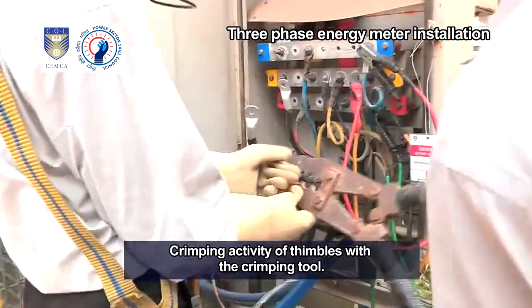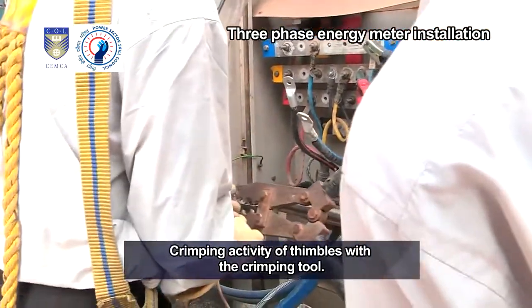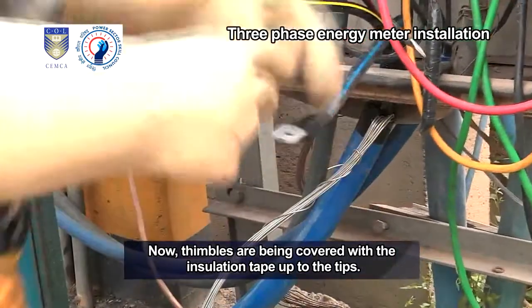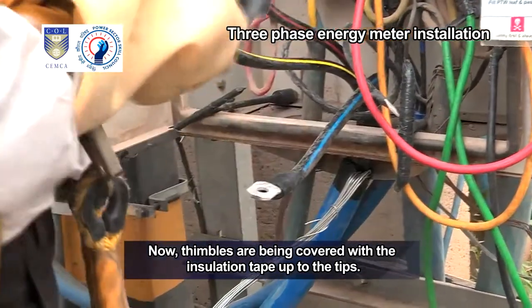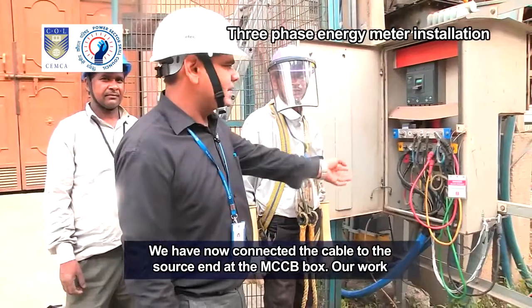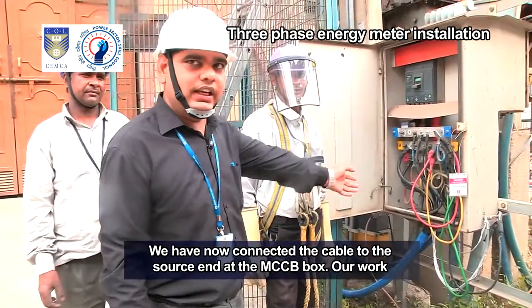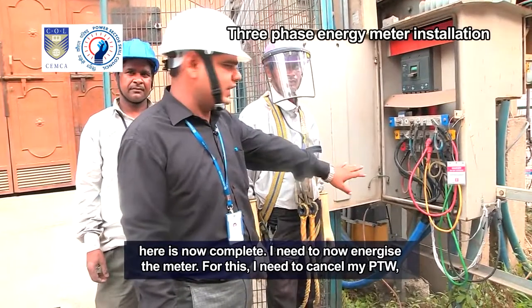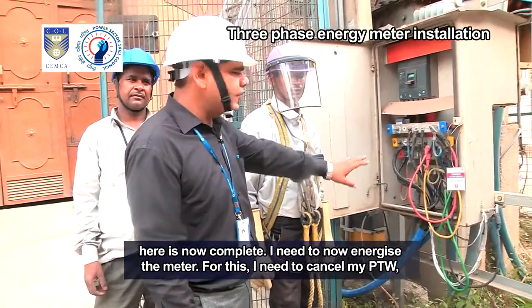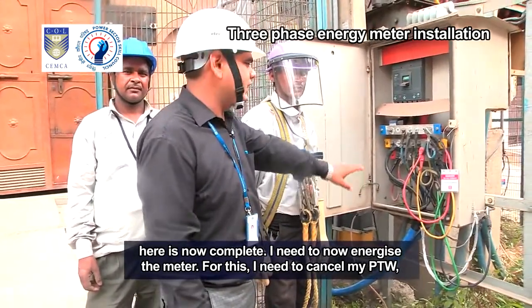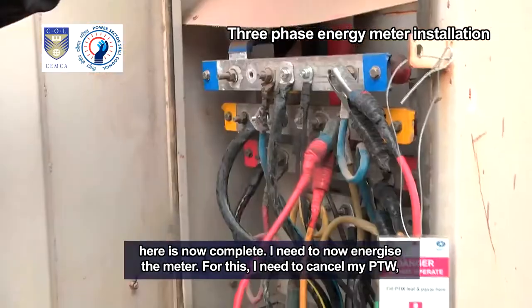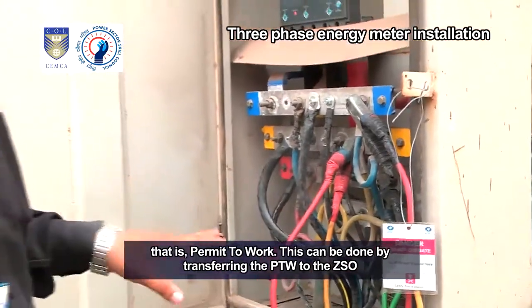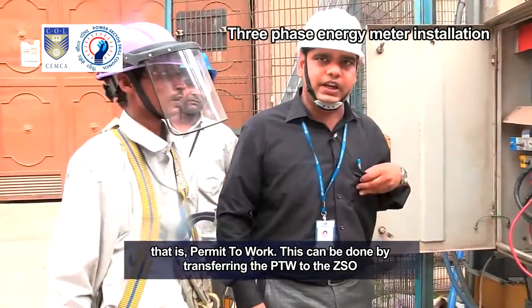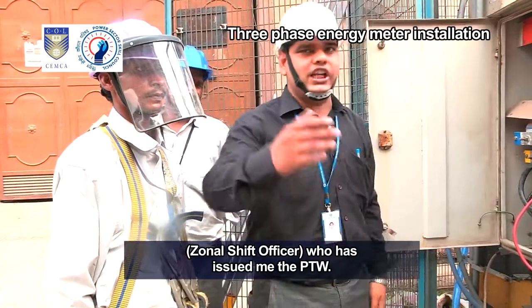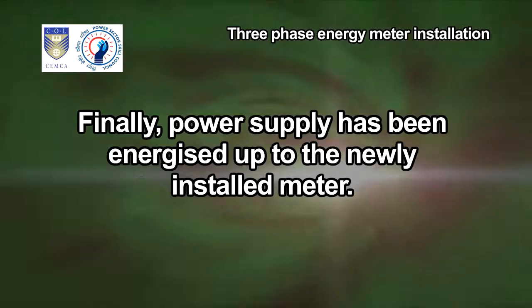main. Crimping activity of thimbles with the crimping tool. Now, thimbles are being covered with the insulation tape up to the tips. We have now connected the cable to the source end at the MCCB box. Our work here is now complete. I need to now energize the meter. For this, I need to cancel my PTW, that is, permit to work. This can be done by transferring the PTW to the ZSO, Zonal Shift Officer, who has issued me the PTW.